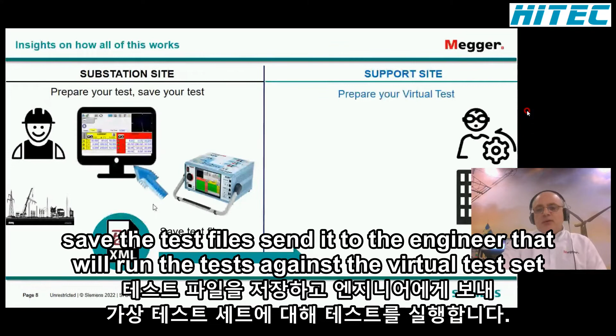Now he connects the virtual test set to the virtual relay, done through an exchange of COMTRADE files, and he can run the test, read the settings and results. He reads the test results, investigates and analyzes using the HMI, the COMTRADE file generated by the relay, and the event recorder, to eventually find a solution - which can be different test plans or different relay protection settings.